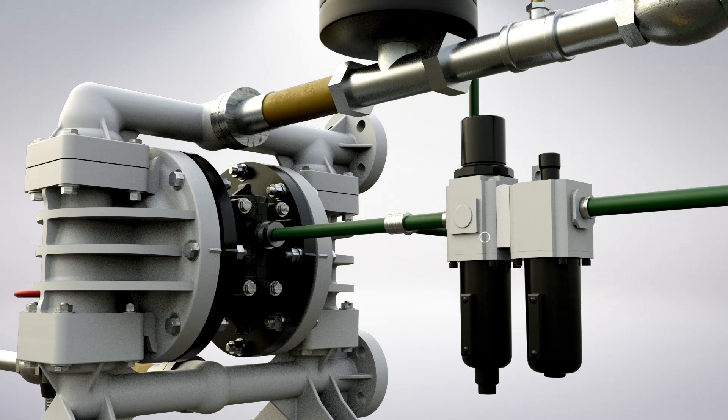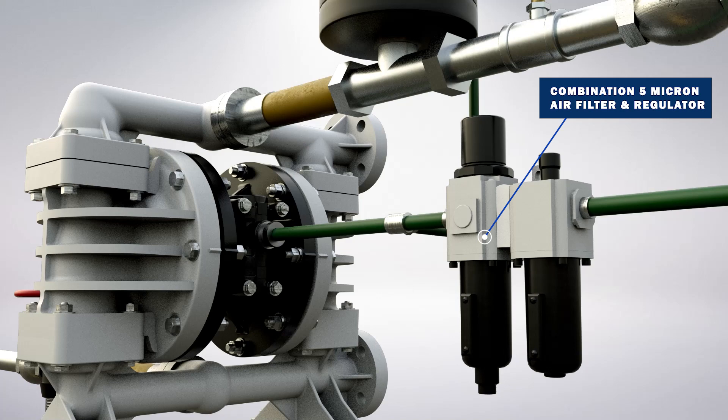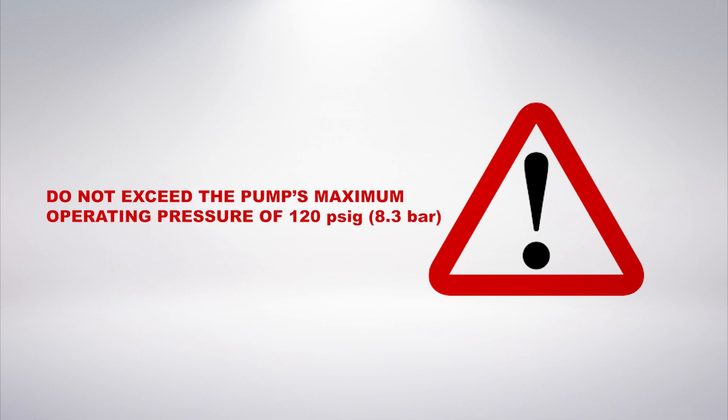For best results, the installation should use a 5 micron air filter, air valve and pressure regulator. The air filter will help eliminate potential pipeline contaminants. Do not exceed the pump's maximum operating pressure of 120 PSIG.